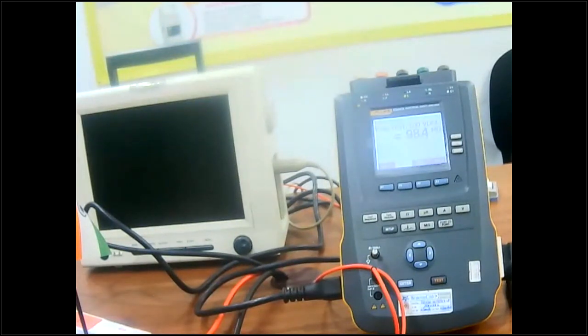And the reason that we do it that way is it's a test that must be done. Remember that we are all conductors. There are electrical current conductors inside the medical device, and the plastic covering is an insulator. So if a human being touches the outside of the plastic, we form an electrical component because we are a conductor. So we have a conductor, an insulator, and a conductor. For those of you who have taken electronics courses already, you know the electronic component that describes conductor, insulator, conductor is called a capacitor. And that's exactly what happens.